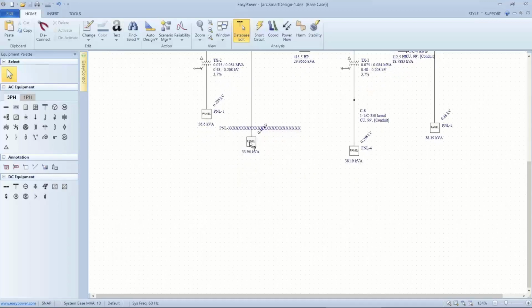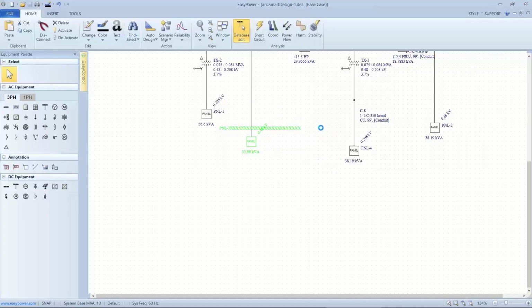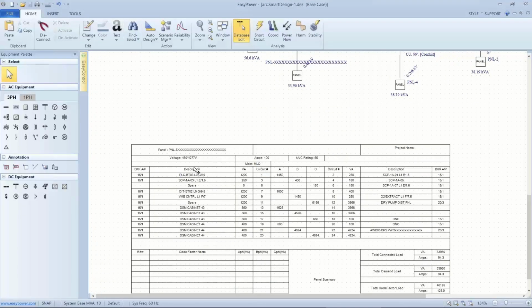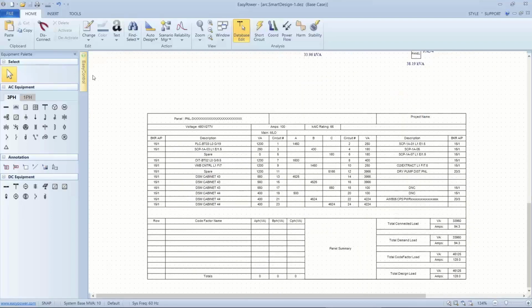Now, the clever thing that I was impressed by is if I now want to put the schedule on my one line, whether it's in a drawing or a one line, the schedule now accommodates that 30 character length. It's like, how cool. So both the name of my panel and the name of the load can include up to 30 characters. Now I'll go you one better.